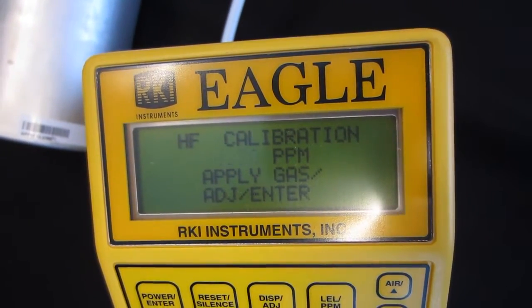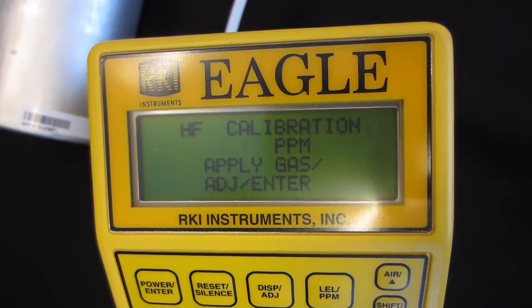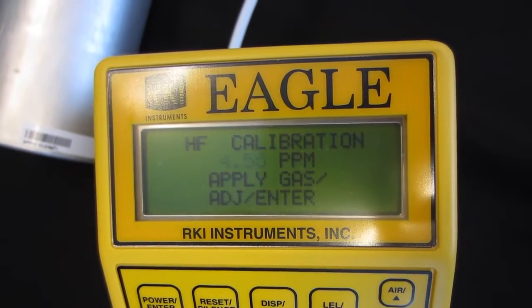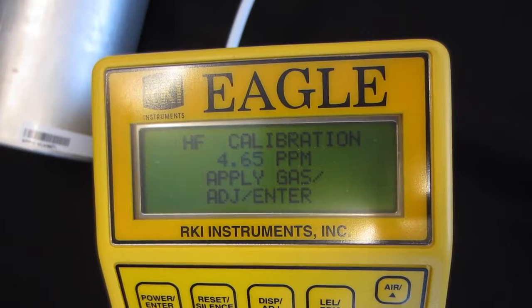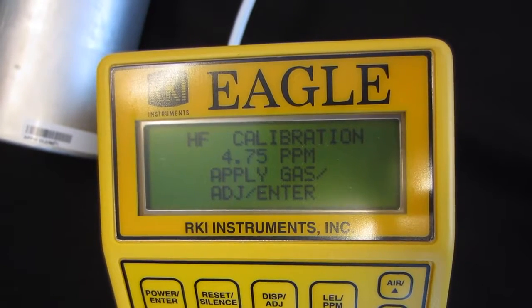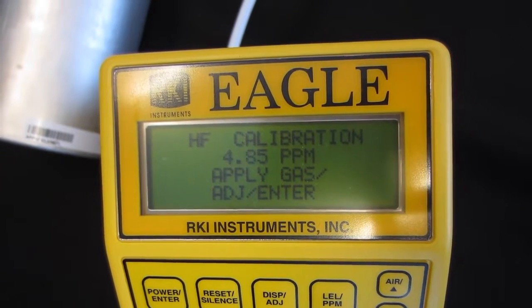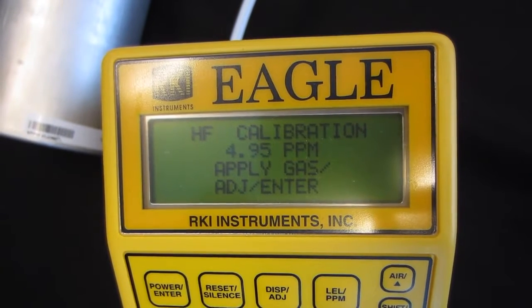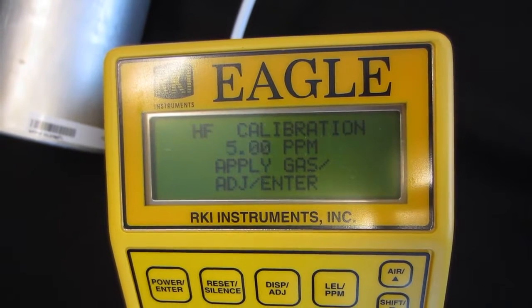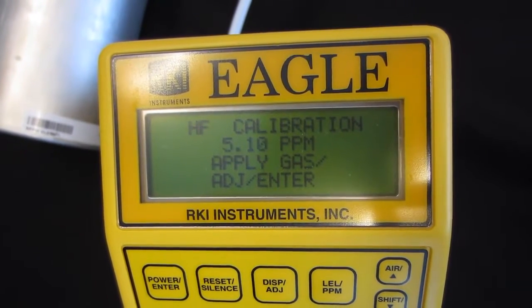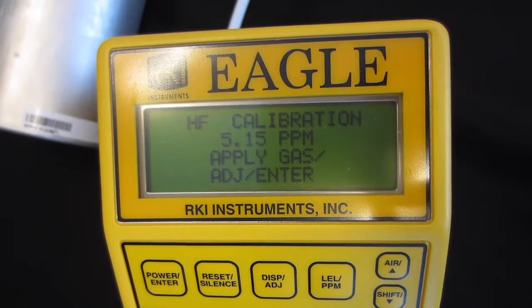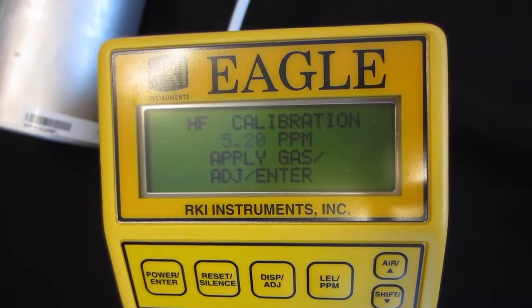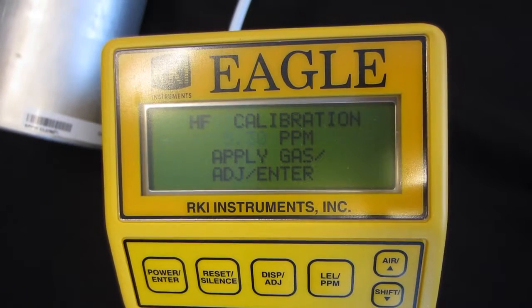So we've been flowing gas for approximately 15 seconds at this point. So it's climbing up steadily. Usually these sensors react fairly quickly, and then they start slowing down as they start getting near the top of their response. As we can see, it is slowing down, 5.20, 25, 30, still going.